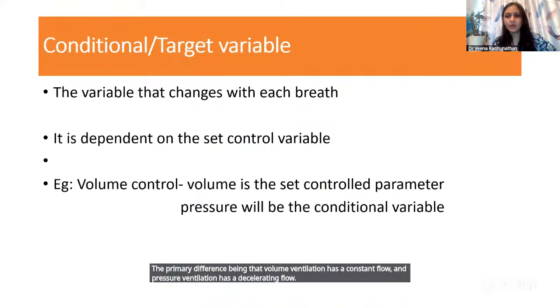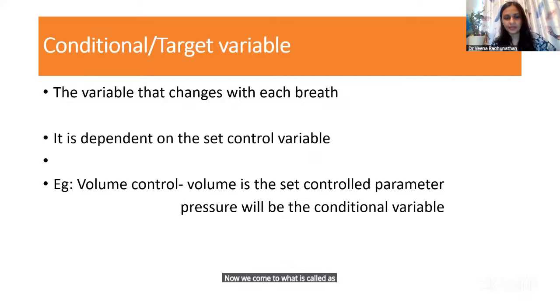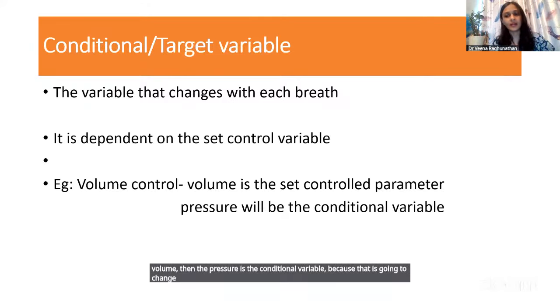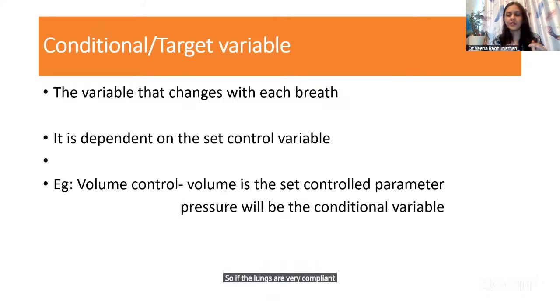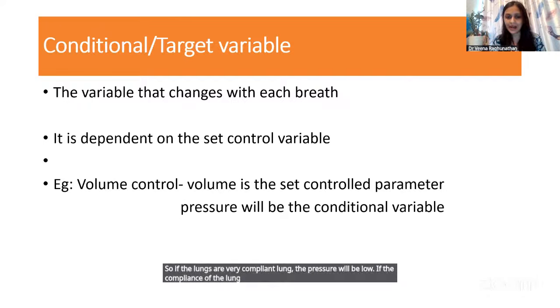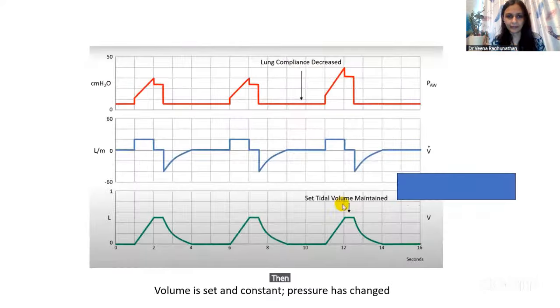Now we come to what are called conditional variables. These are the variables which change with every breath, so it depends on the set control variable. For example, if I set volume, then the pressure is the conditional variable, because that is going to change depending on the lung characteristics. If the lung is very compliant, the pressure will be low. If the compliance of the lung is bad, then the pressure is going to be high.